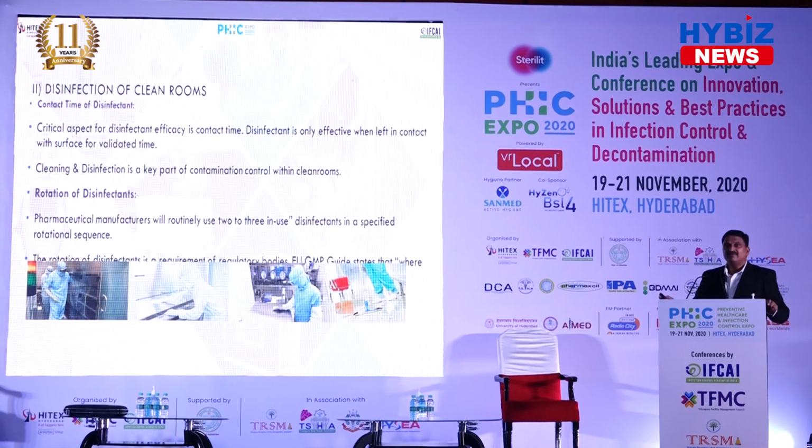The contact time of a disinfectant is very important. During disinfectant validation or efficacy testing, the contact time will be evaluated, and any disinfectant applied on a surface should be held for a validated contact time. And cleaning and disinfection is the key part of contamination control in clean rooms.